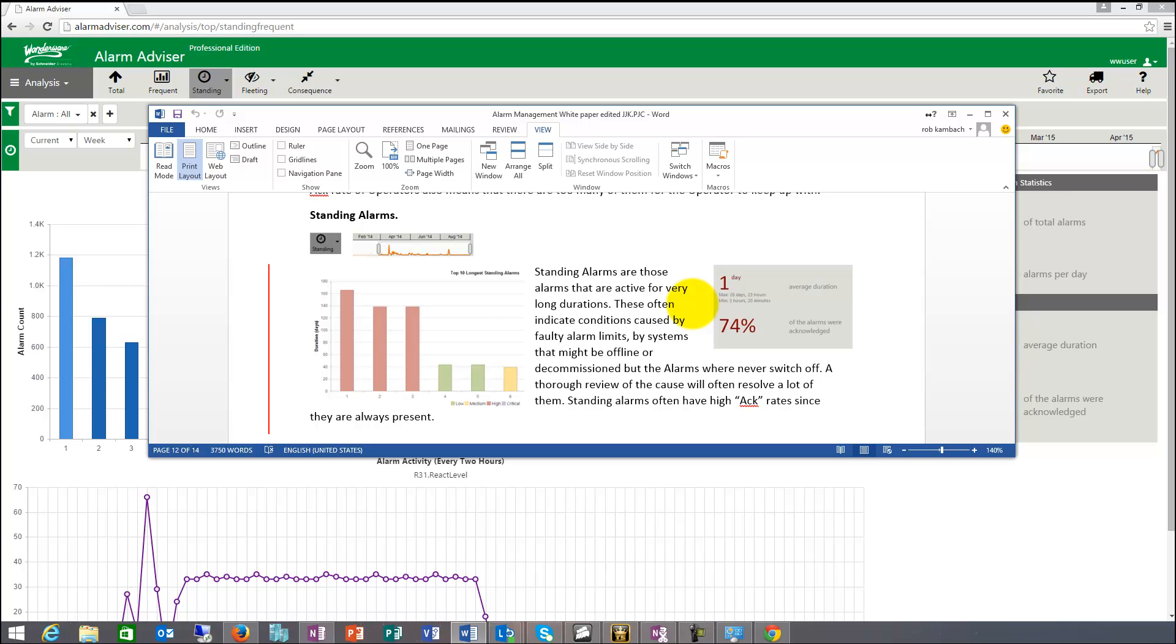So things that you could use here, a plant state suppression, you could use shelving, you could use tools to tell the system that these systems are offline and so they don't have all these standing alarms all the time. It might be also decommissioned, but the alarms were never switched off. A thorough review of those will often resolve a lot of them.